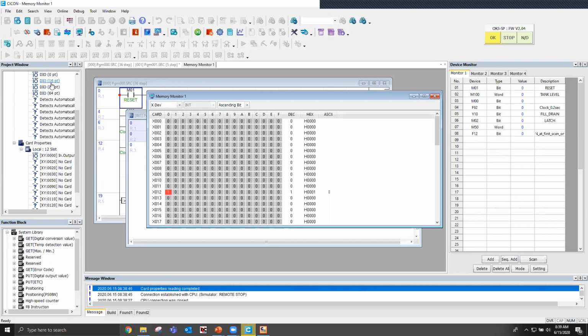When we step down to the 16 points, the default IO card, you get 1 word of X and 1 word of Y for that module. When we step up to the 32 point, you go back up to 2 words - from 16 to 32, that's 2 words. Then from 32 to 64, we jump up 2 more words, because we're adding on 2 more words. So altogether, we'll have 4 words of X and 4 words of Y for our 64-point module. Hopefully that makes sense.